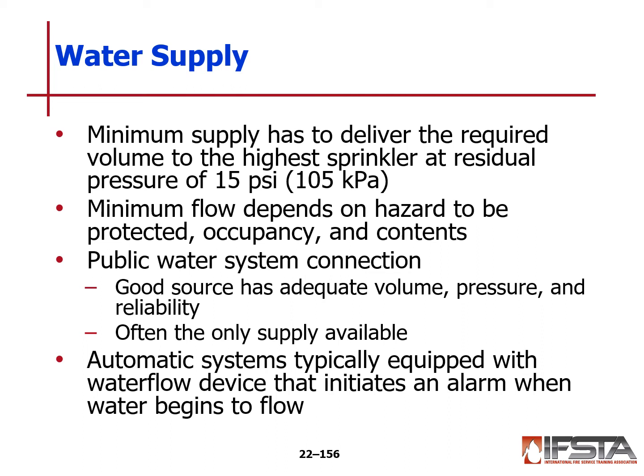Water supply: a minimum supply has to deliver the required volume to the highest sprinkler at residual pressures of at least 15 psi. The minimum flow depends on the hazard to be protected, the occupancy, and the contents. Public water system connections: a good source has adequate volume, pressure, and reliability, and is often the only supply available. Automatic systems are typically equipped with a water flow device that indicates an alarm when water begins to flow.